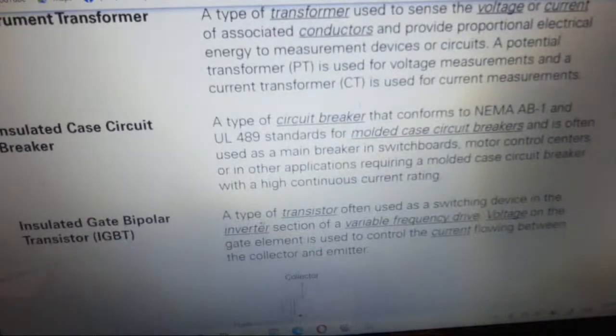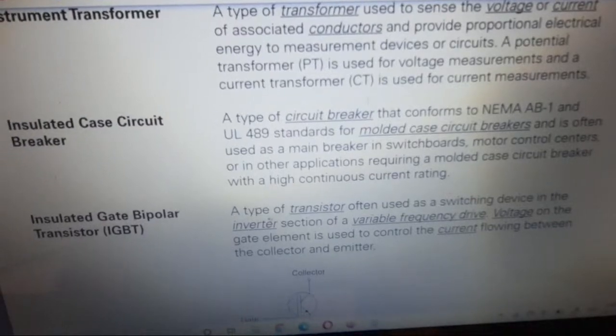Insulated case circuit breaker, a type of circuit breaker that conforms to NEMA AB1 and UL 489 standards for molded case circuit breakers and is often used as a main breaker in a switchboard, motor control center, or in other applications requiring a molded case circuit breaker with a high continuous current rating.